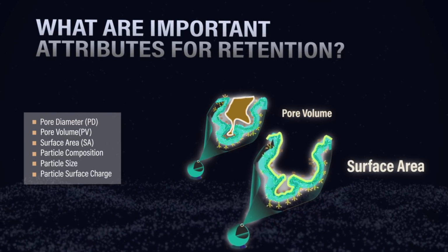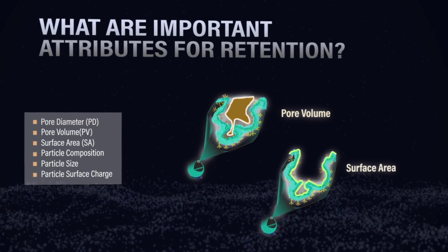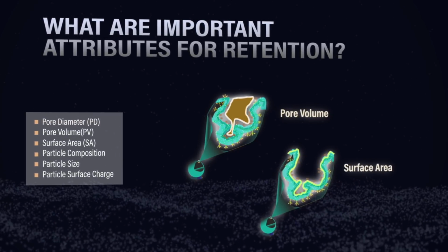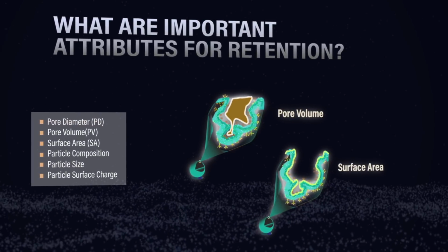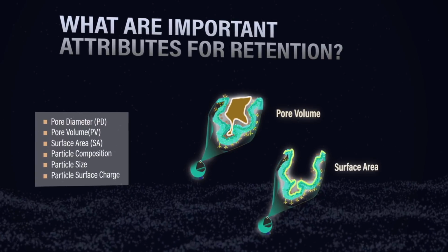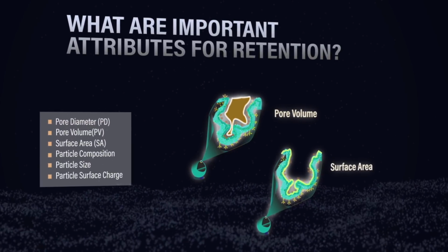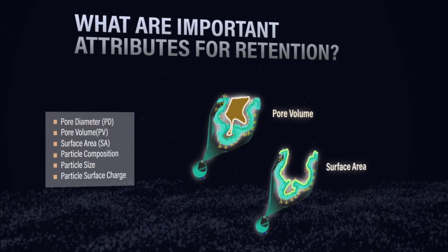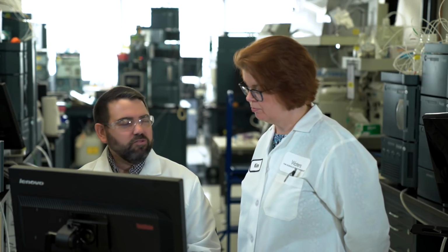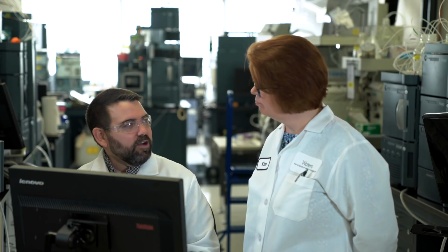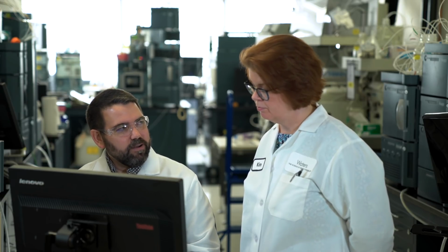The actual surface coverage, how much C18 you're actually putting down, can impact the retention as well. And then you have to think of other things too, like metals maybe potentially in the older phases. Embedded polar groups that we talked about in another episode all impact the selectivity. The surface charge, whether it has a slight positive charge, can play a huge role in how that L1 column performs. So understanding those is very important.